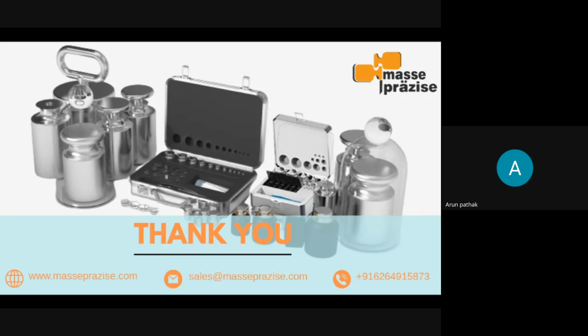Murthy sir has asked which value has to be considered for weighing, either nominal value or conventional mass. Sir, I will suggest using the conventional mass value, because the nominal value is different. The nominal value is fixed, that is a weight of 200 gram is called 200 gram, but it may have a conventional mass value of 200.005 also. So for the calculations or for the verifications, the conventional mass should be used.